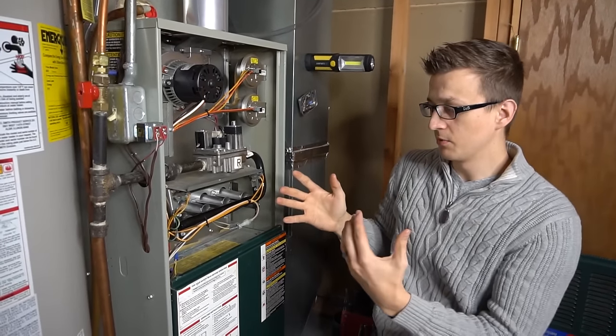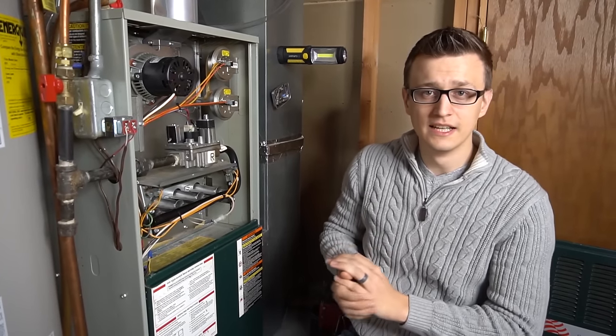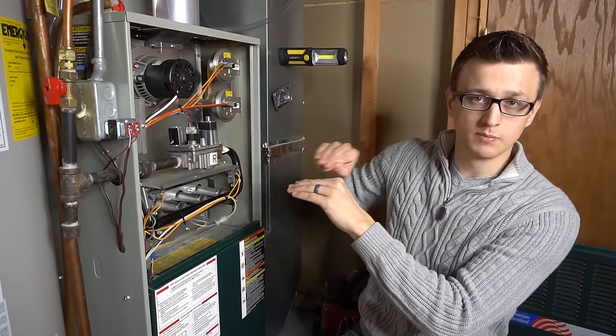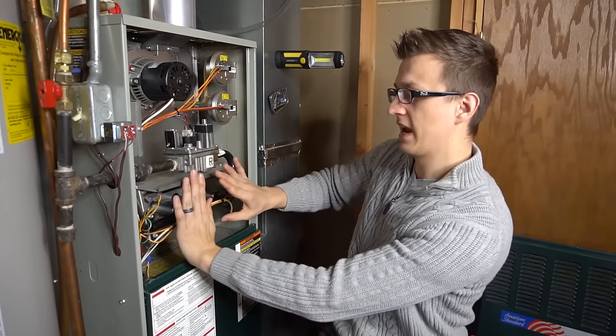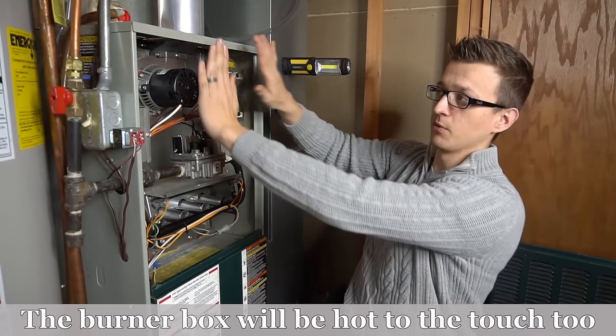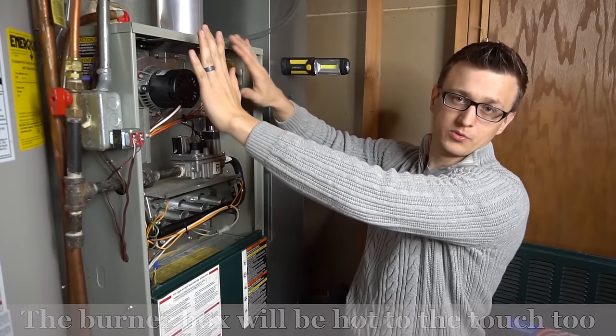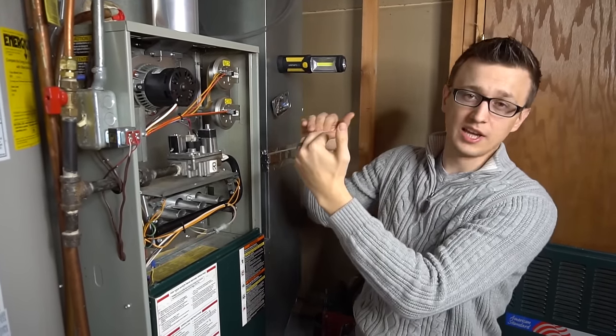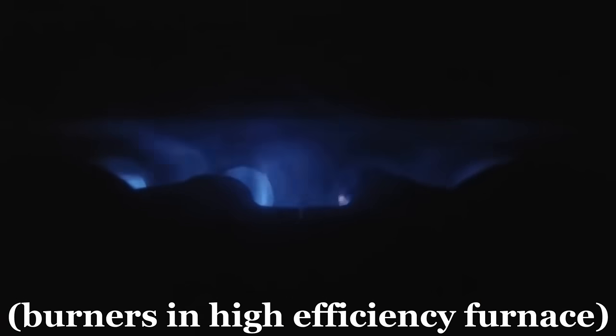What happens is, for some reason, either your heat exchanger is plugged or has a crack or hole in it, and the flames that are supposed to be pulled through are starting to push back. A lot of times if you put your hands in front of the burner box, you'll feel some hot air coming backwards towards you, or if you're seeing flames rolling backwards or the flame patterns are lazy all over the place, that's a pretty bad sign too.